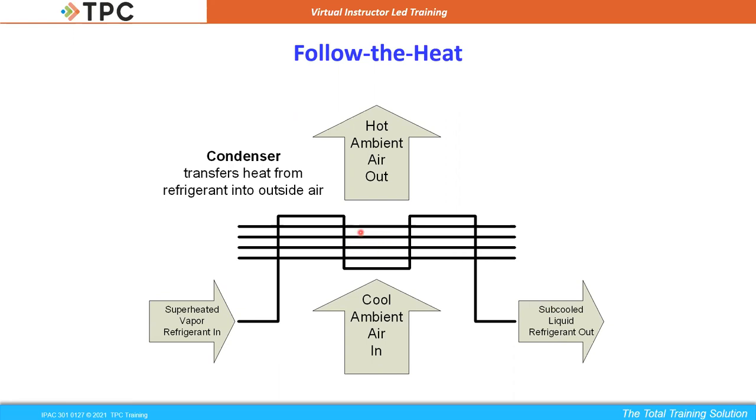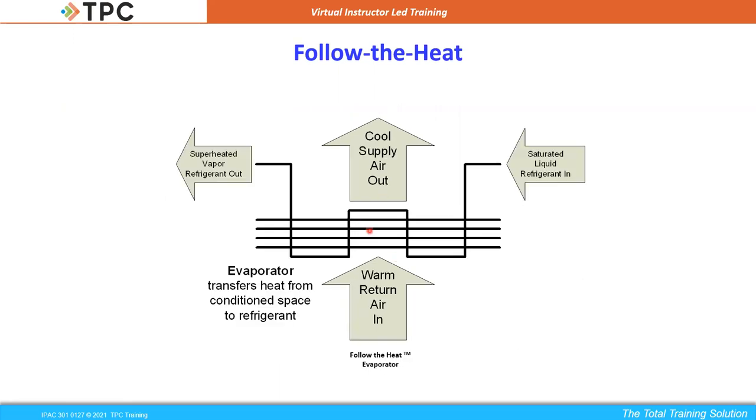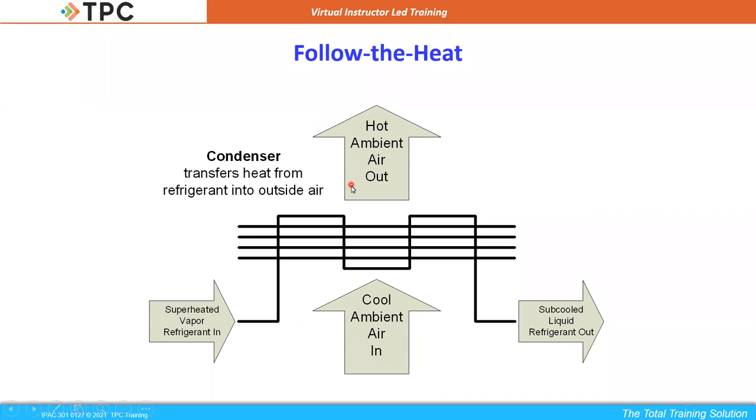So for subcooling, we're checking the difference between what we got as a vapor and liquid mixture compared to what we get when we're 100% liquid on the other side. So we're measuring the liquid level inside the condenser for subcooling. And as we saw here for superheat, we're measuring the saturation temperature, comparing what we have for going from a liquid to a vapor to 100% vapor. It's very important that both of those are dialed in to the exact point we want them to be.